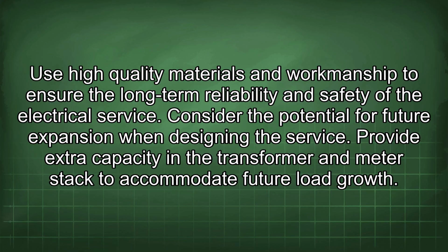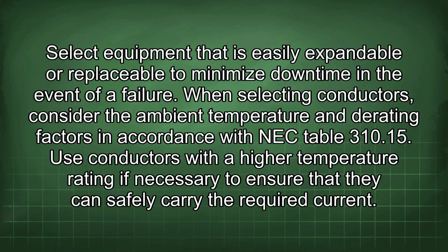Consider the potential for future expansion when designing the service. Provide extra capacity in the transformer and meter stack to accommodate future load growth. Select equipment that is easily expandable or replaceable to minimize downtime in the event of a failure. When selecting conductors, consider the ambient temperature and derating factors in accordance with NEC Table 310.15. Use conductors with a higher temperature rating if necessary to ensure that they can safely carry the required current.